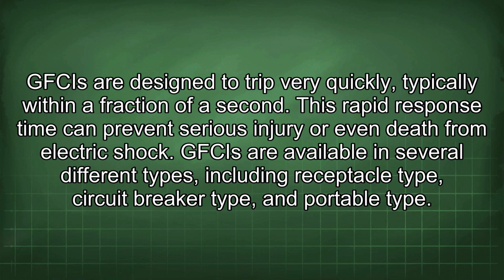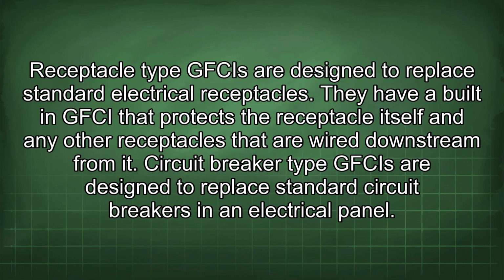This rapid response time can prevent serious injury or even death from electric shock. GFCIs are available in several different types, including receptacle type, circuit breaker type, and portable type. Receptacle type GFCIs are designed to replace standard electrical receptacles. They have a built-in GFCI that protects the receptacle itself and any other receptacles that are wired downstream from it.